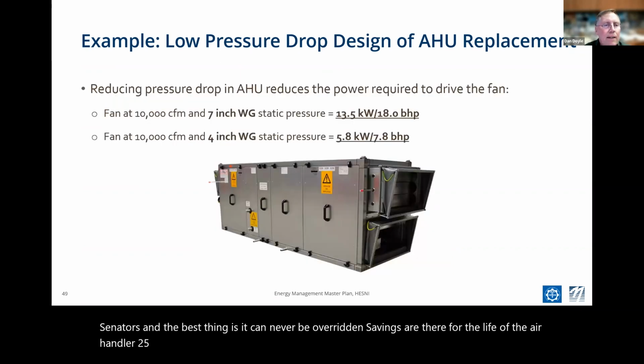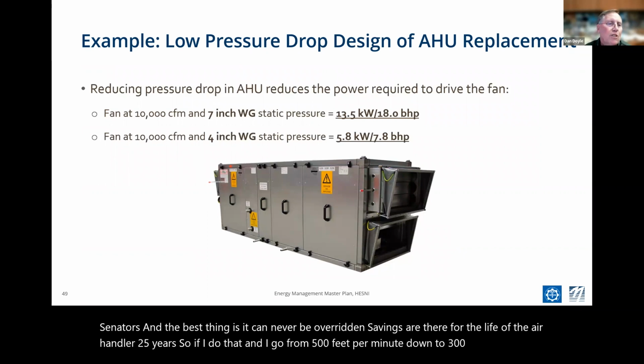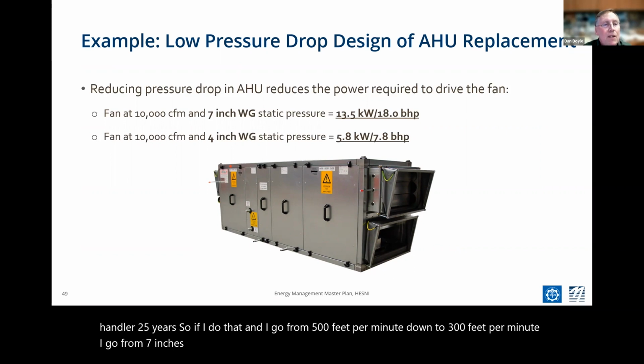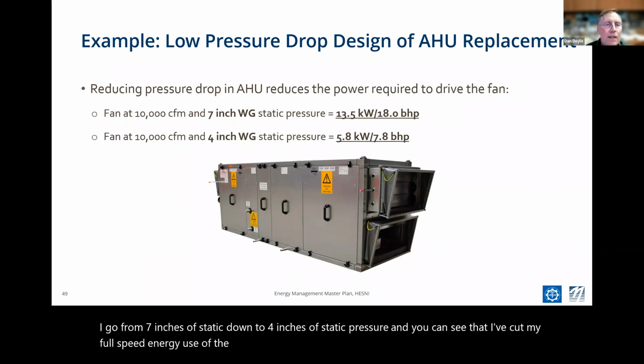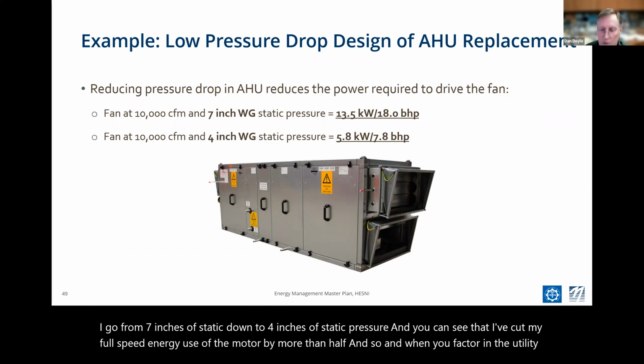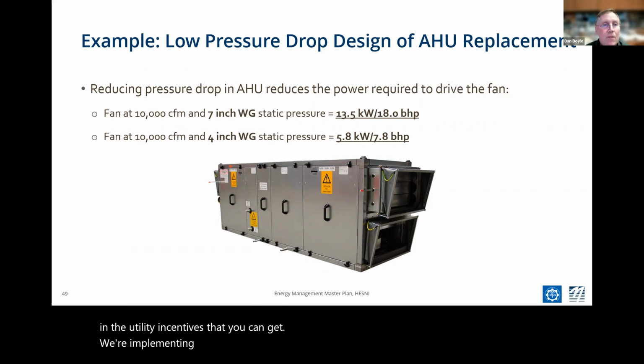So if I go from 500 feet per minute down to 300 feet per minute, I go from 7 inches of static down to 4 inches of static pressure. And you can see that I've cut my full speed energy use of the motor by more than half. And when you factor in the utility incentives that you can get for implementing this, you can usually find there's no increase in first cost.